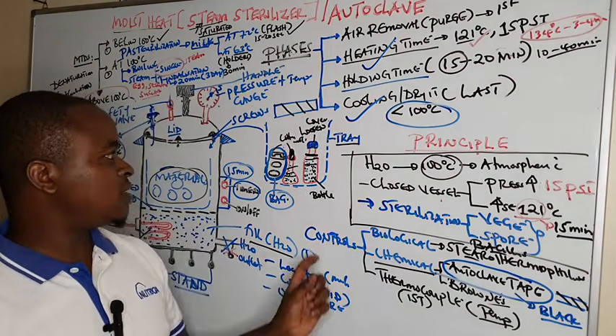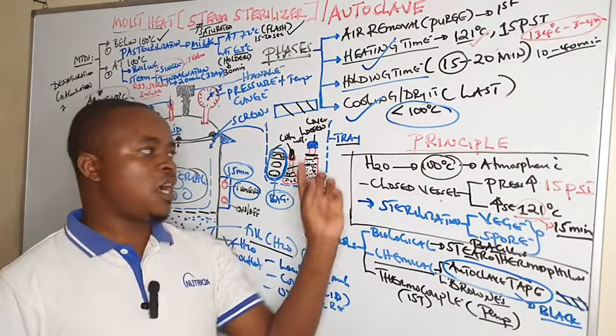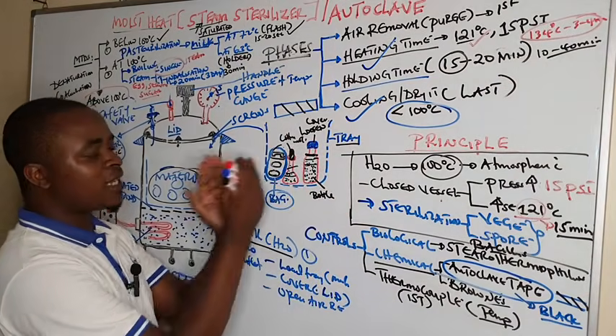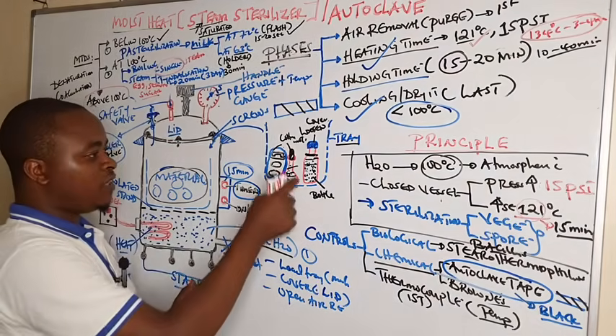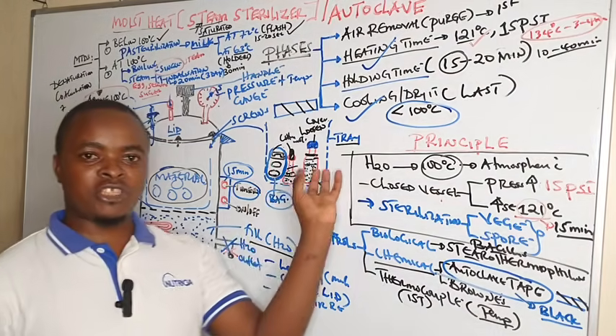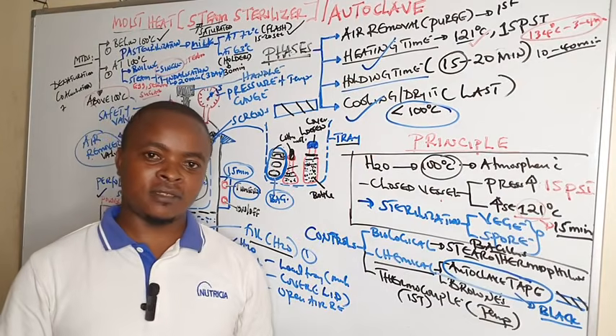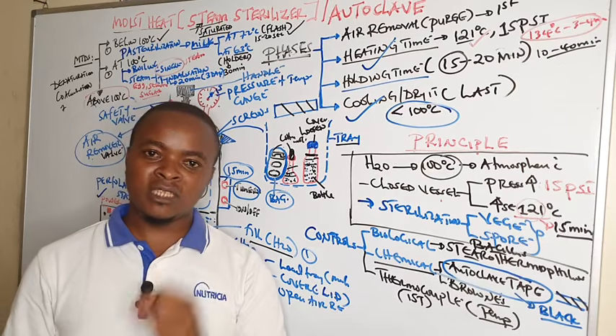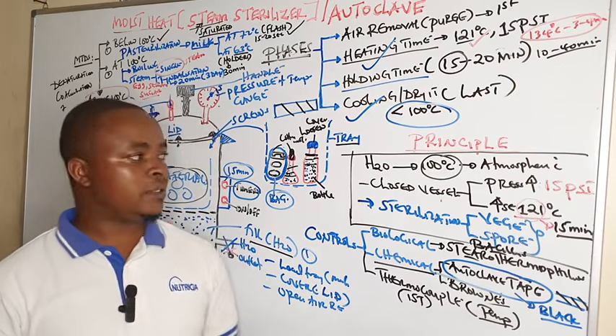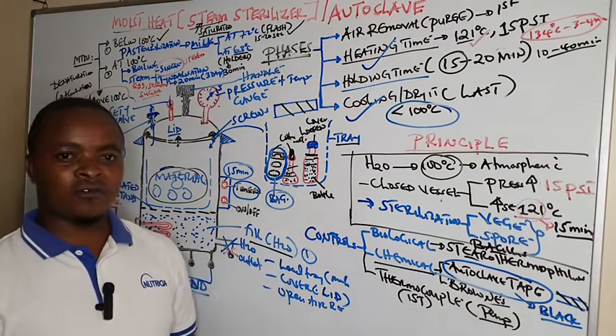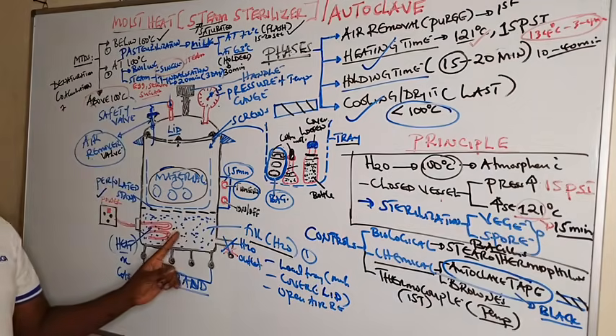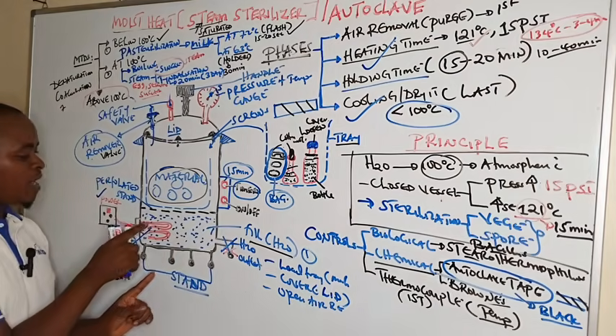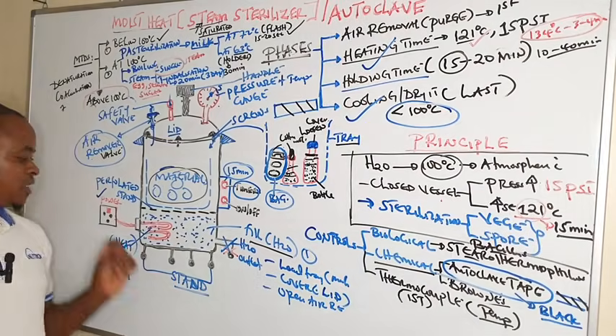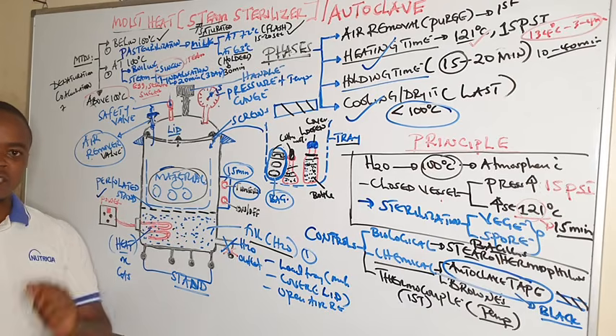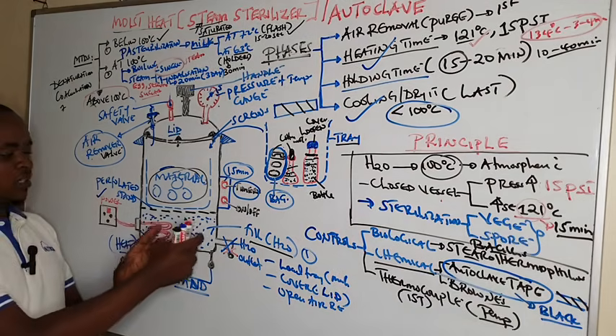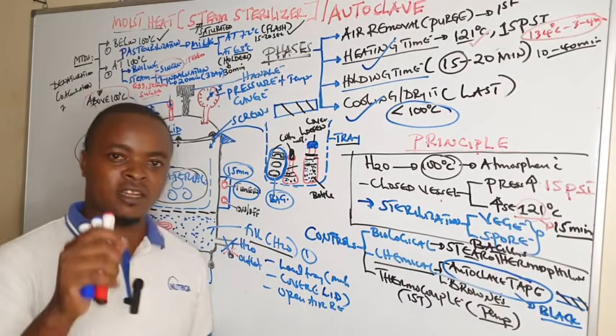And another thing which affects it is failure to use controls and also overpacking materials in a tray without leaving spaces where steam can reach each article being sterilized. That is also very important to note when you are autoclaving materials. Always leave enough space. And please always check the water level. We said the water level should be above the heater when you're using an electric autoclave. It is also very important to always check the level of the water in the autoclave.